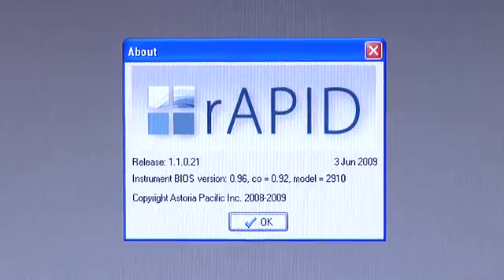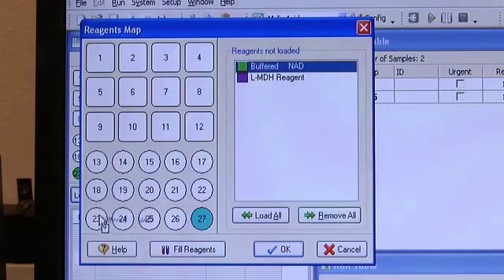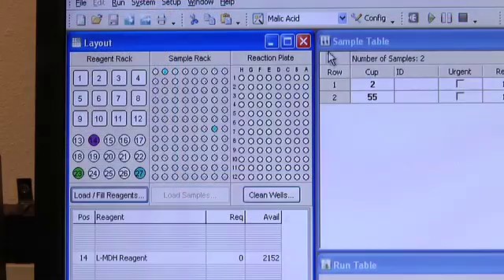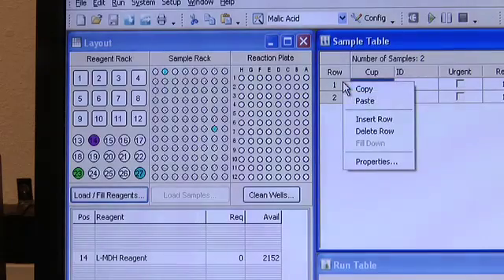All of the hardware components of the Astoria discrete are controlled by our custom designed RAPID software. RAPID is responsible for assigning the tests in the highest order of efficiency and automatically performs system calibration and supervises general maintenance of the system. RAPID is designed to be flexible, easy to use and highly efficient.